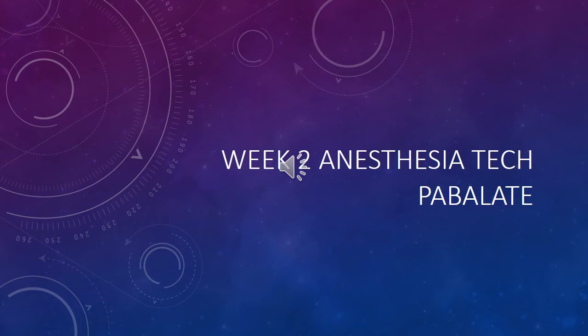I'm using isoflurane because the math is easy on this, okay? We said that a MAC of isoflurane is what percent? 1%. So if I have 1% of isoflurane, this is called volumes percent. I say it that way because that means that for whatever volume you're running through the vaporizer, 1% of it on the other side, on the outflow of that vaporizer, when it rejoins on the variable bypass trap, will be isoflurane.